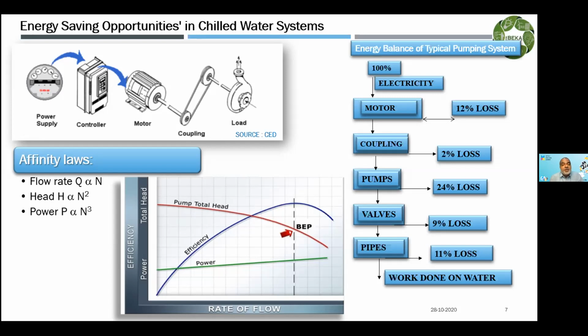So without studying the load, the motor was driving the pump. The motor was considered in isolation, and people replaced the standard motor with an energy efficient motor even though the pump was correctly sized. Here only one parameter was considered, the efficiency. The rest of the motor's parameters, and its relation with the pump affinity law, were not considered. Let us evaluate what happens in this case.